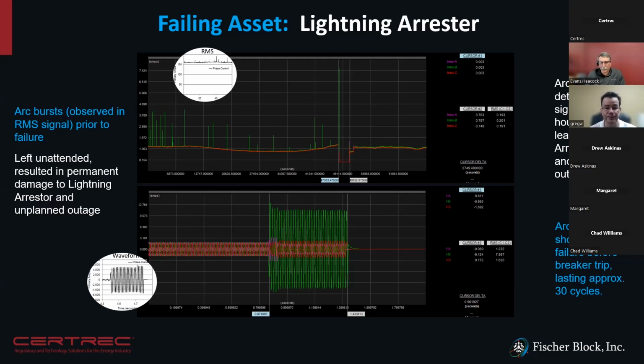So just real quick, you've kind of brought up sampling rates. Talked about it and how you sample. What is the sampling rate of the Fischer blocks? How fast do they sample? Well, it's a good question, because most people believe that the higher the sample rate, the better. And in certain applications, that's true. And in this case, out on the grid, 128 samples a cycle is our typical sample rate. If you sample faster than that, in many cases, you just end up with more data than you need to analyze the problem. But 128 samples a cycle has been sufficient for the predictive analytics and the waveform capture during breaker trip out on the grid.